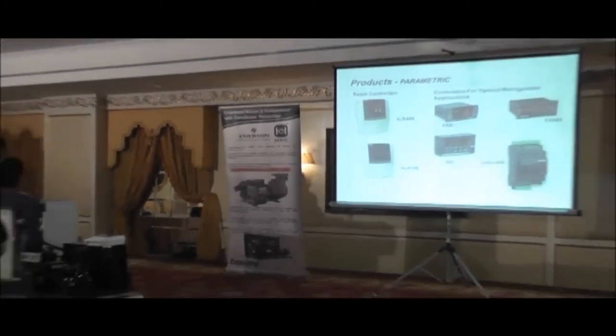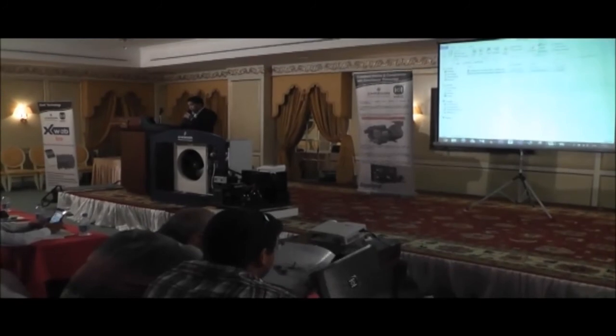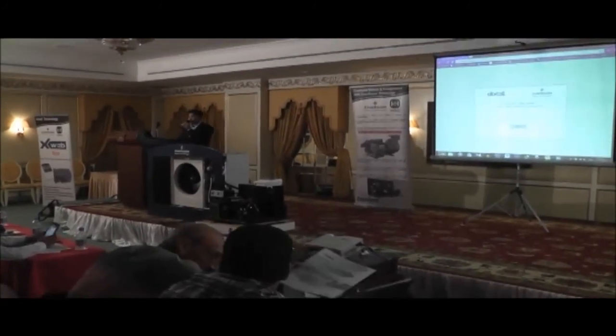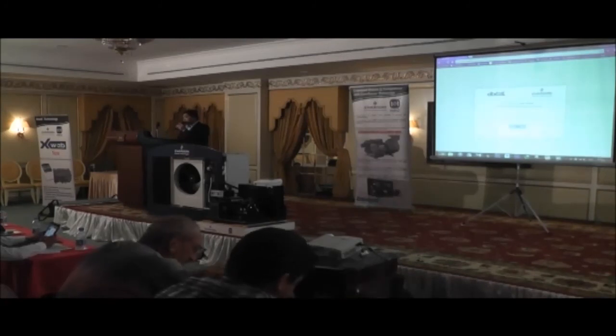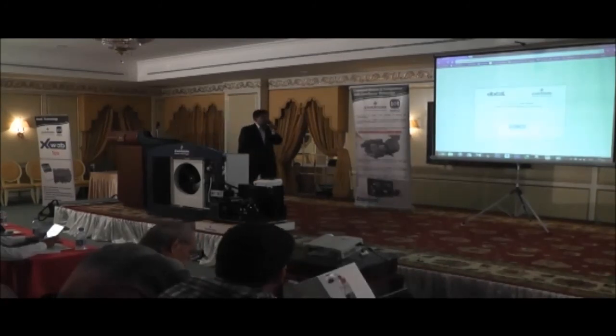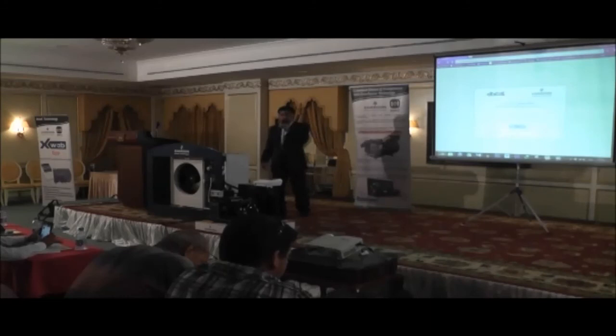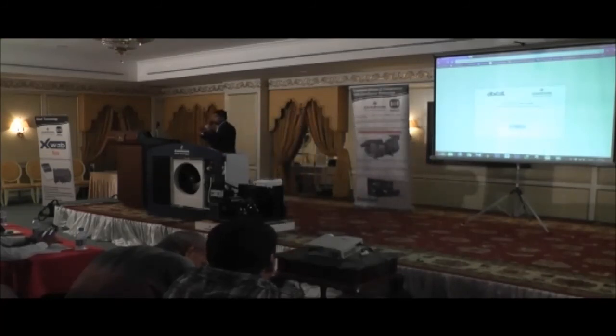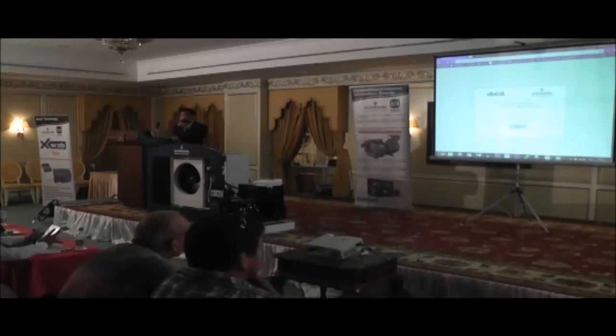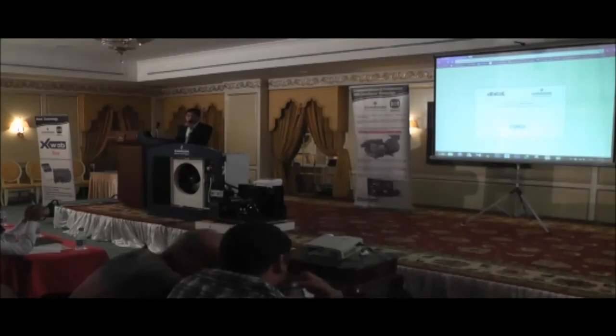So let me just walk you through the actual Dixell server website. The XWeb will not require any special software. You just need to use an IP address. If you have your laptop or computer, just an IP address. Because in setting up the XWeb, you need to assign a fixed IP address so that you can type the IP address, for example 192.168.1.1, into the Explorer, and then you can have this main page.